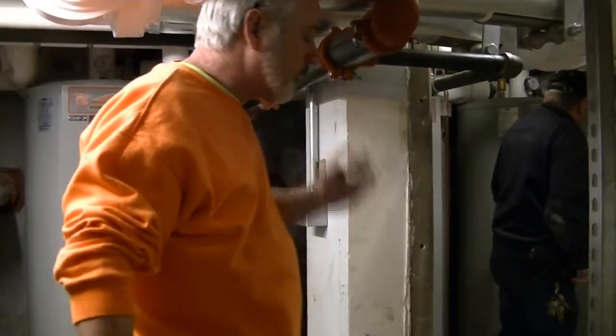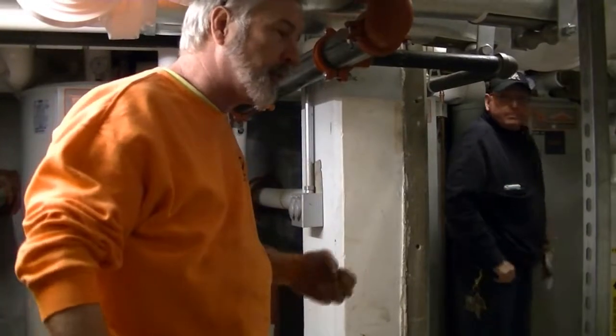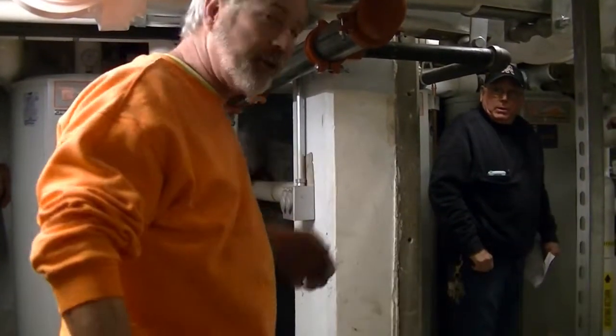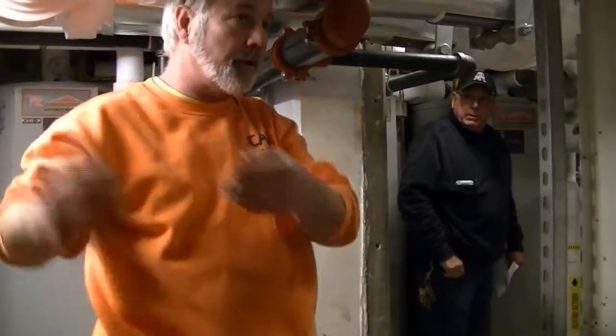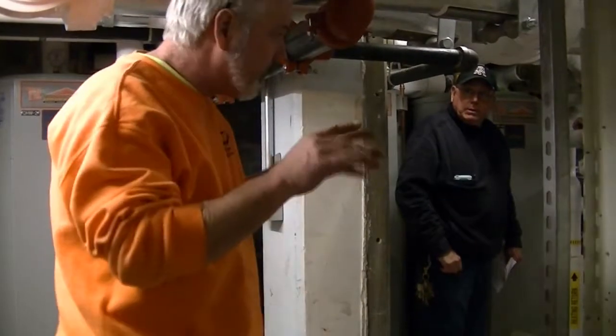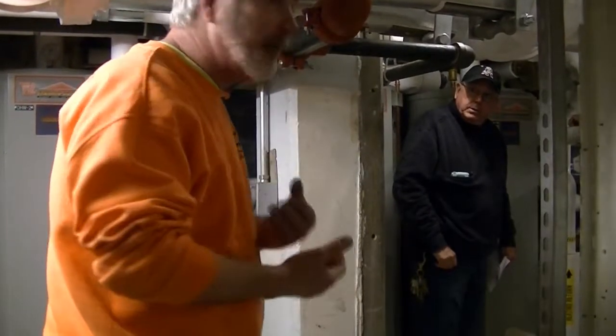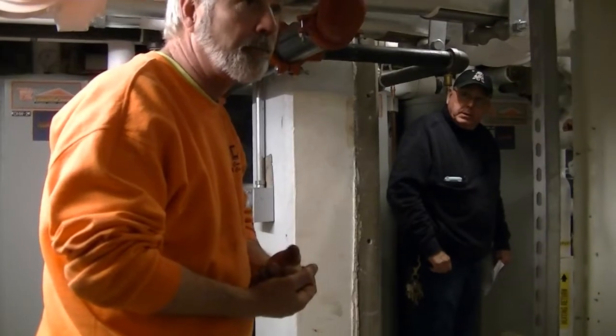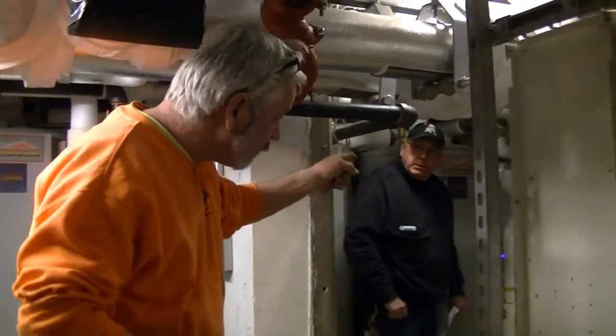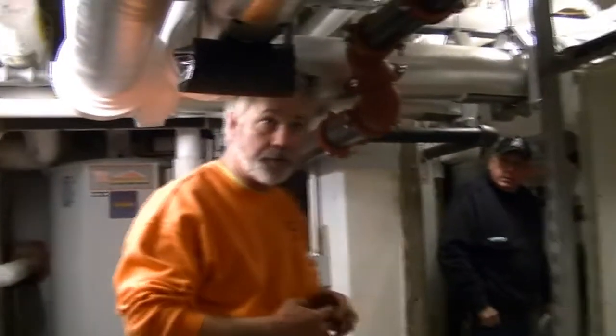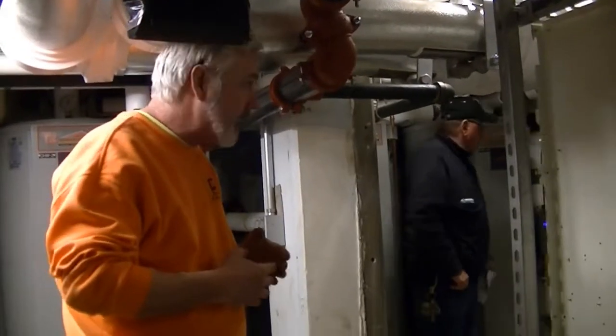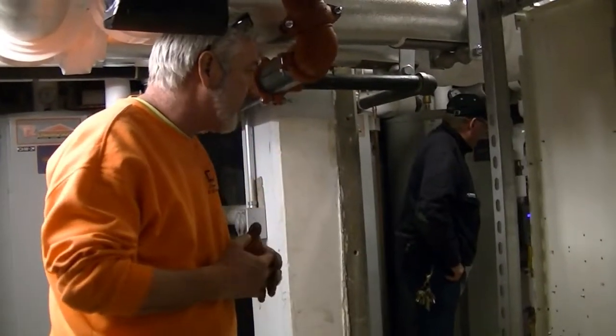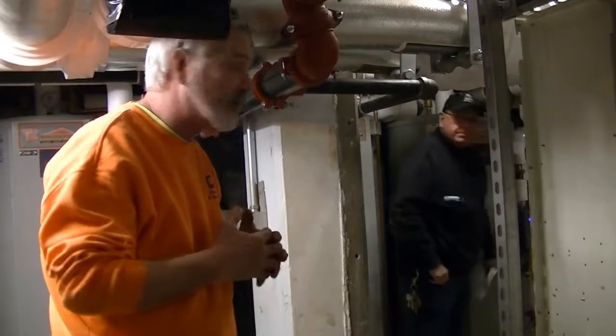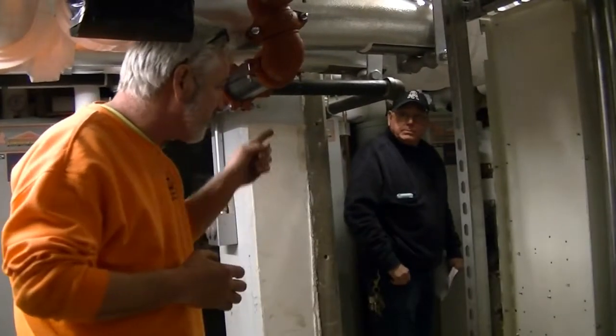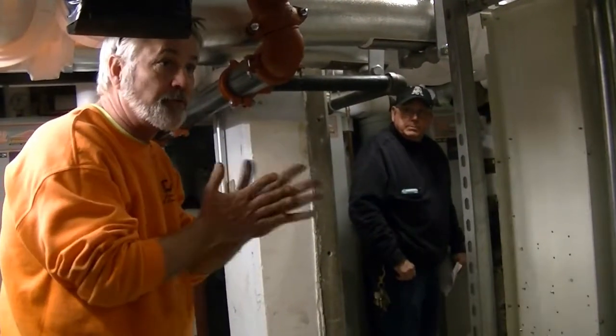So some of the problems we've had: because we have no domestic hot water, the heating system's down. You know, I put somebody in front of the cascade panel, they bring it up and say, no, you have domestic hot water being produced. The problem is your mixing valve's not sending it out to the building. Okay, it's happened before, so before you say the boilers are broken, there's no domestic hot water, make sure your domestic hot water system's working on the plumber's side.